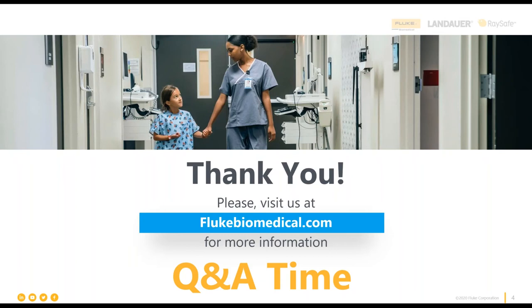The first question: what's the main difference between the 615 and 612? The 612 and 615 are very, very similar. There's a good diagram on flukebiomedical.com under the products tab, then electrical safety analyzers, that highlights the differences between the 612, 614, and 615. But the largest difference between the 612 and 615 is onboard automation — the ESA 615 does have onboard automation and can be used as a standalone device without a PC, where the 612 doesn't. Both devices can be used with our OneQA or any of our other workflow automation platforms.